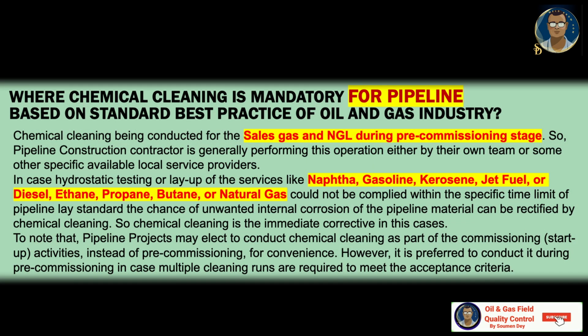Chemical cleaning is conducted for sales gas and NGL during the pre-commissioning stage. The pipeline construction contractor generally performs this operation, either by their own team or by some other locally available service providers. If hydrostatic testing or layup of services like naphtha, gasoline, kerosene, jet fuel, diesel, ethane, propane, butane and natural gas could not comply with the specific time limit of pipeline layup, the chance of unwanted internal corrosion of the pipeline material can be rectified by chemical cleaning.